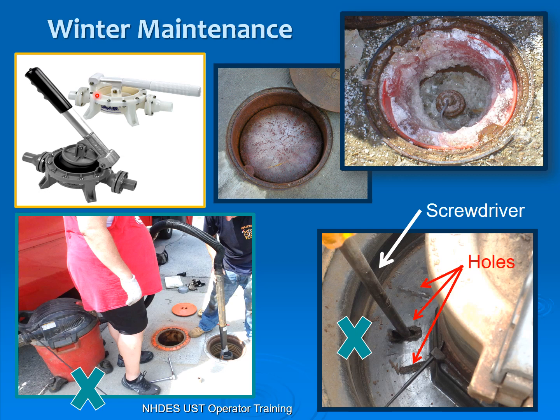Types of hand pumps to pump your sumps out and your spill buckets out — this is a good safe hand pump to use. Do not use your shop vac to suck out your spill bucket. You're sucking out product — heating oil, diesel, gasoline — into a motorized unit with electricity and sparks. I've seen these vacs, when they've been vacuuming around during an inspection, pop their lids four or five feet in the air. It's an accident waiting to happen: gasoline vapors, an electric motor, a spark, and kaboom.